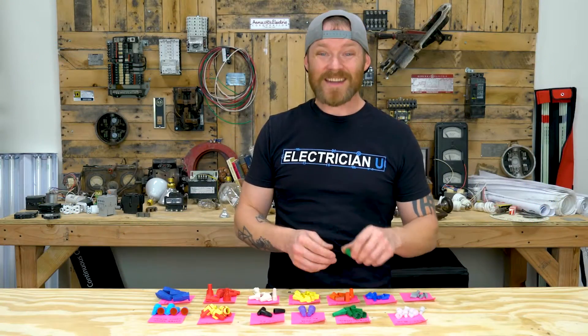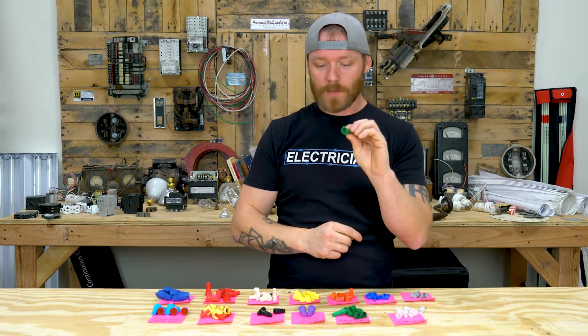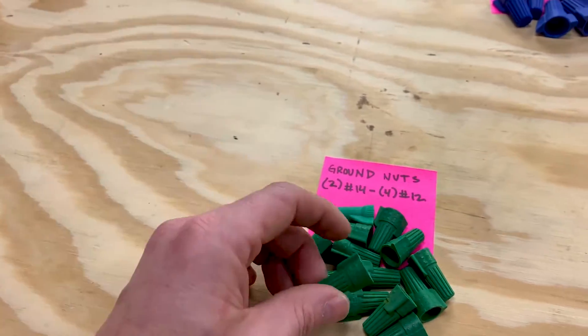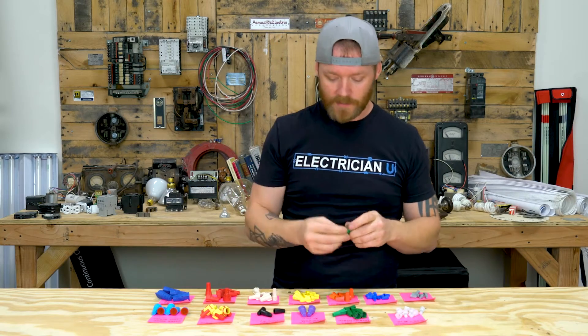Next up are the greenies — green ground wire nuts. These are specifically designed for grounds and are pretty much like a red as far as what they can hold, same spring and build, two 14s up to four 12s. The unique thing is there's a hole right in the center. Say you've got three grounds but only need one coming out — you'd bunch all three, but you want one to come out at the end. So you put this wire nut over all of them to keep them tightly together while allowing one to exit. It's a very specialized thing you're only going to use for grounds.